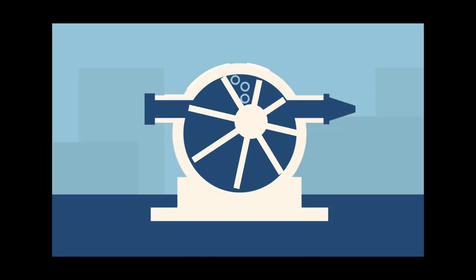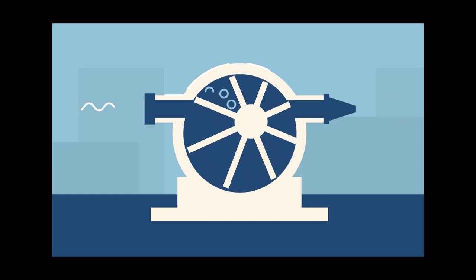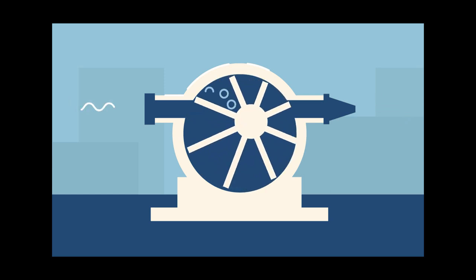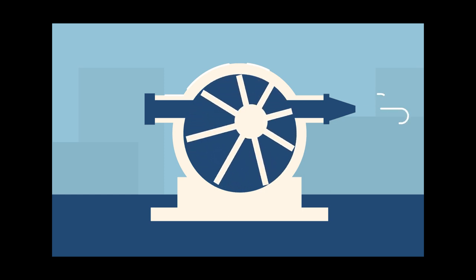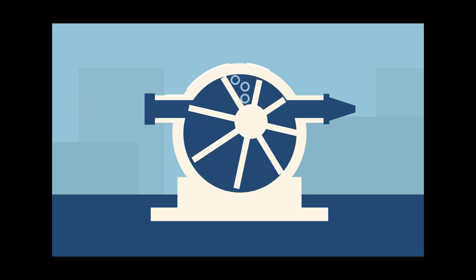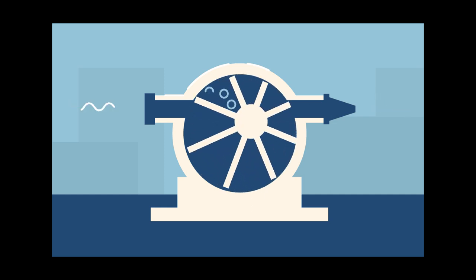The rotary vane is another type of compressor, although it's an aging technology and it's found much less frequently than it used to. The rotary vane uses a flywheel with little vanes that protrude from the wheel and extend to contact the walls of an oval-shaped chamber. The chamber is largest at the suction port and tapers down, compressing the vapor until it reaches the exit port.